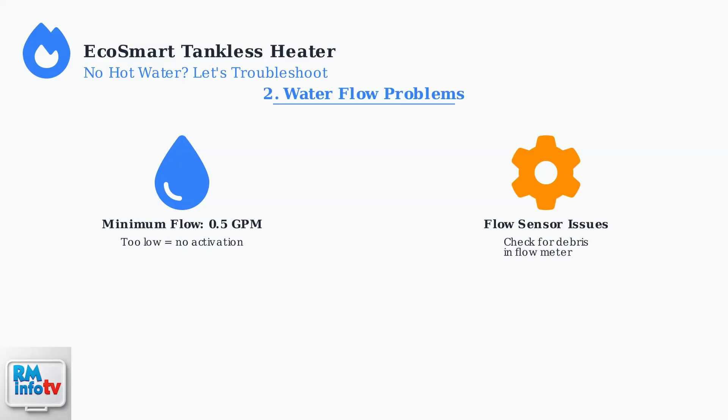A faulty flow sensor or debris caught in the flow meter can prevent the unit from detecting water flow, even when water is flowing normally through the system.